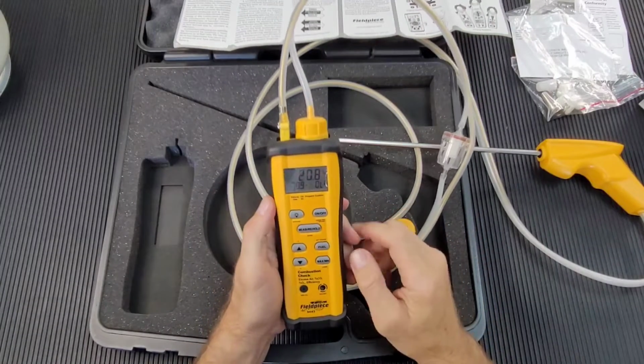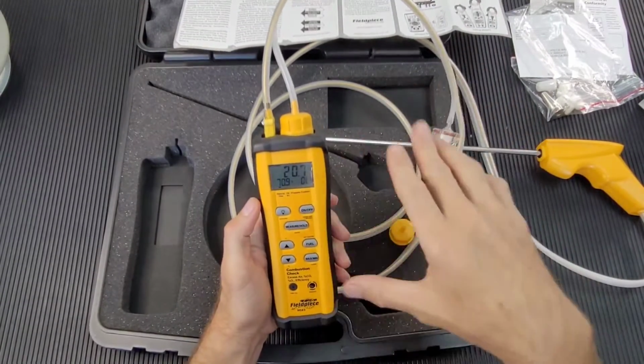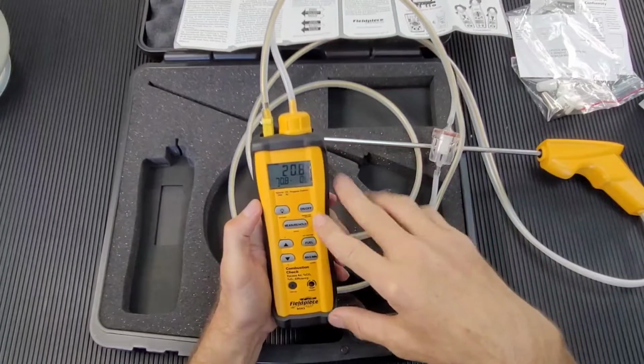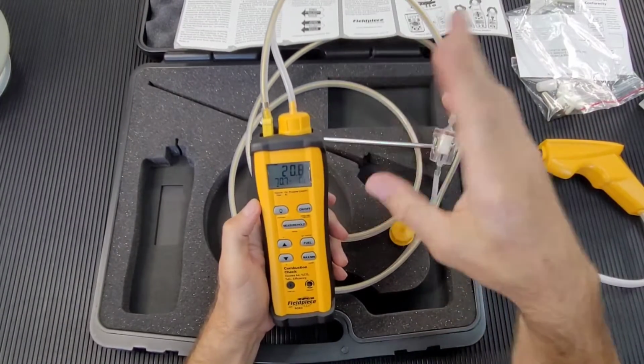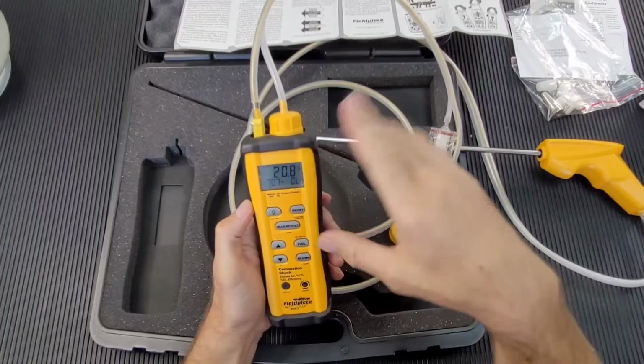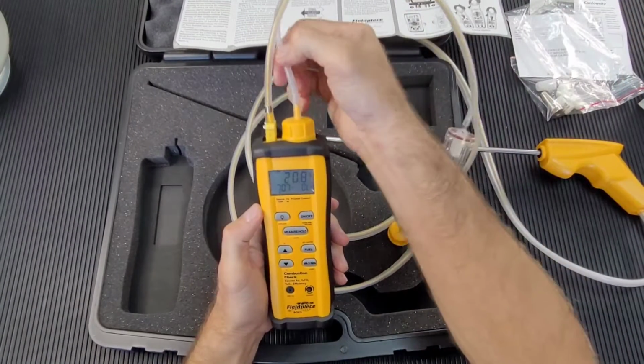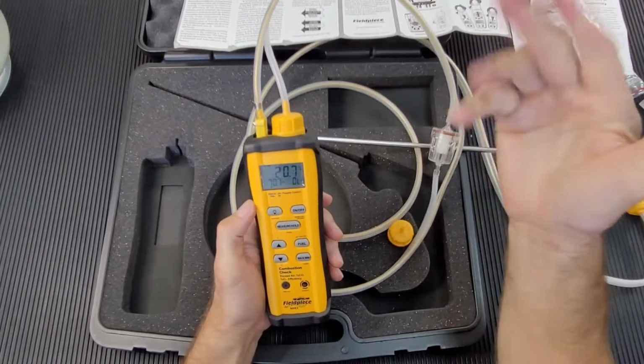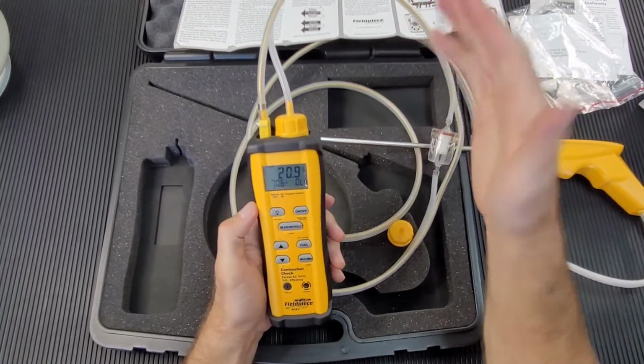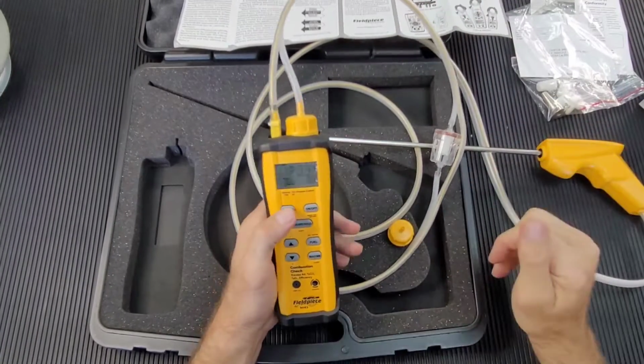Okay. Now, it's not uncommon for electrochemical sensors, when you turn them on and off or when the pressure changes, to change a few tenths of a percent. That's very normal, okay, folks? If we even just restrict it a little bit, see, it's a response to the pressure change, and that's very normal. Don't have to freak out about that.